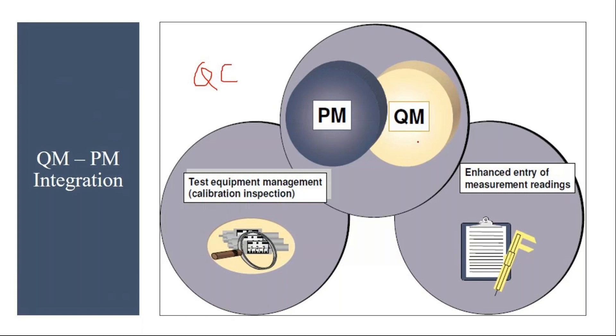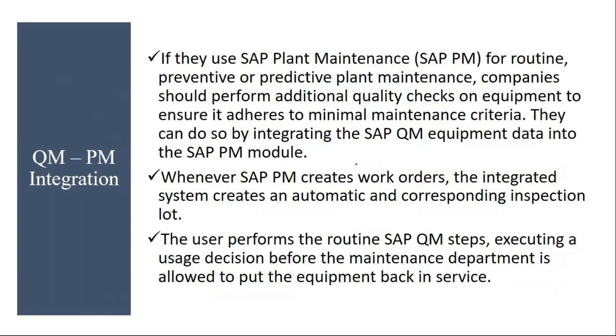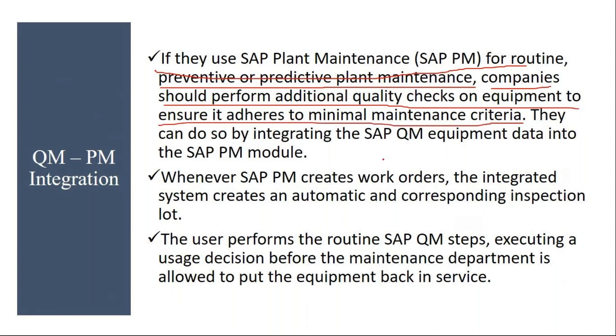In QM we call it calibration inspection, and the same business process in the PM module is called test equipment management — that is the integration basically. If they use SAP PM for routine preventive or predictive planned maintenance, companies should perform additional quality checks on equipment to ensure it adheres to minimal maintenance criteria.